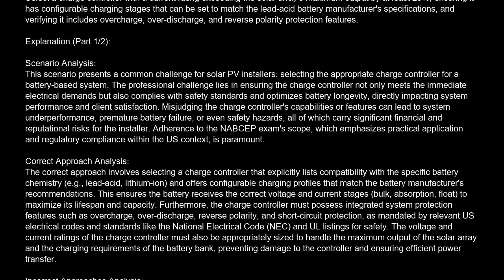Furthermore, the charge controller must possess integrated system protection features such as overcharge, overdischarge, reverse polarity, and short-circuit protection, as mandated by relevant U.S. electrical codes and standards like the National Electrical Code, NEC, and UL listings for safety. Voltage and current ratings of the charge controller must also be appropriately sized to handle the maximum output of the solar array and the charging requirements of the battery bank, preventing damage to the controller and ensuring efficient power transfer.